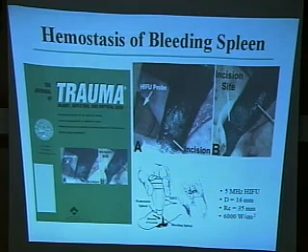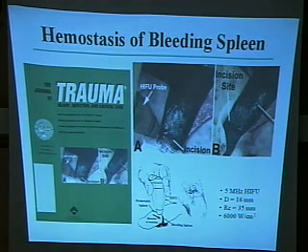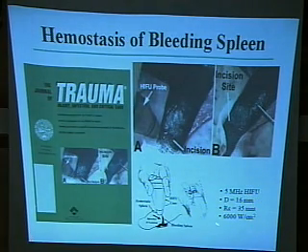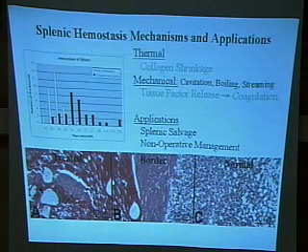You see a little different frequency. That goes to show the different tissue properties between liver and spleen. The 3.3 or 3.5 that I showed for liver did not work for spleen. And also you can see the high intensity values as compared to liver, which was 2,000. Here we're dealing with about 5 to 6,000 watts per centimeter squared.